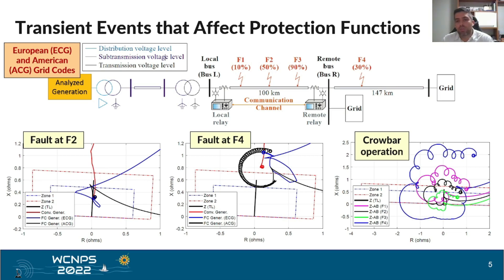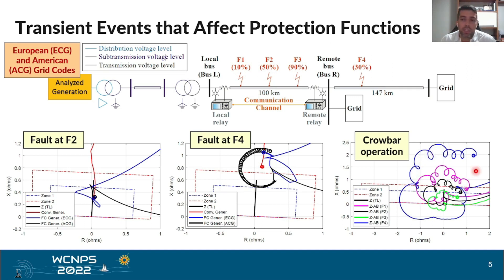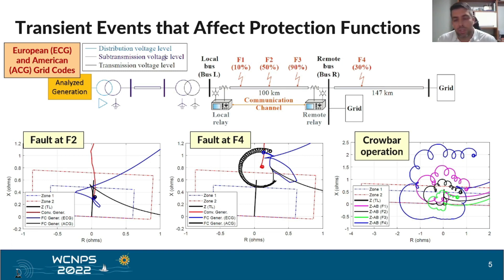The same conclusion can be drawn if we consider a crowbar operation in a Type 3 wind power generation. Again, we can see some oscillations in the apparent impedance trajectory calculated by the distance relay, which could pose problems for protection performance. These events are transient in nature and cannot be represented in phasor simulations.